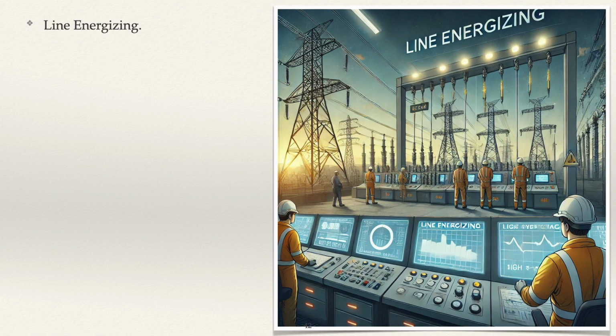K. Line energizing. The purpose is to ensure the safe and successful energization of the transmission line and its integration into the grid. The inspection focus on 1. Supervising the pre-energization checks, including insulation tests, grounding system checks, and conductor integrity tests. 2. Monitoring the energization process to ensure that the line is free from faults and operates as expected under load conditions.